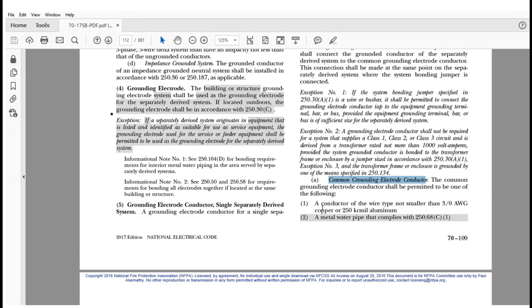And the next item that it had in 2014 said, or the metal frame of a building or structure that is connected by a bonding jumper, not smaller again than 3/0 copper or 250 kcmil, to the grounding electrode. So if it didn't have a concrete encased electrode, but it was the building frame, and it jumped over to the grounding electrode system that was established, and it was 3/0 copper or 250 kcmil of aluminum, then you were okay.